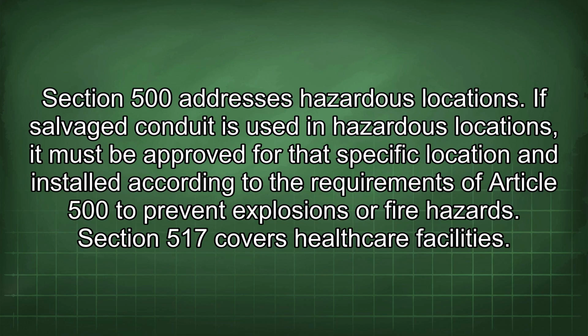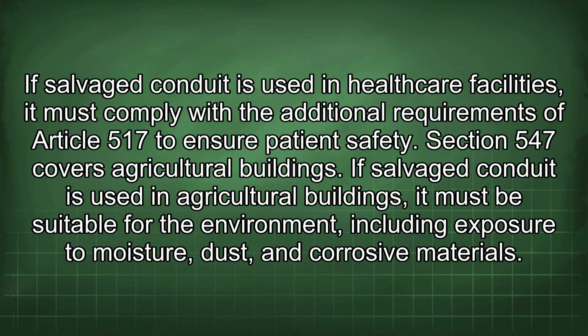Section 500 addresses hazardous locations. If salvaged conduit is used in hazardous locations, it must be approved for that specific location and installed according to the requirements of Article 500 to prevent explosions or fire hazards. Section 517 covers healthcare facilities. If salvaged conduit is used in healthcare facilities, it must comply with the additional requirements of Article 517 to ensure patient safety. Section 547 covers agricultural buildings. If salvaged conduit is used in agricultural buildings, it must be suitable for the environment, including exposure to moisture, dust, and corrosive materials.